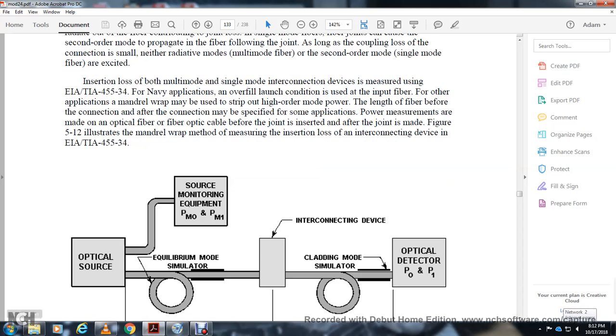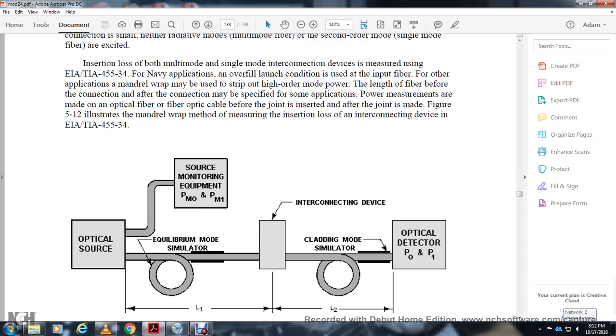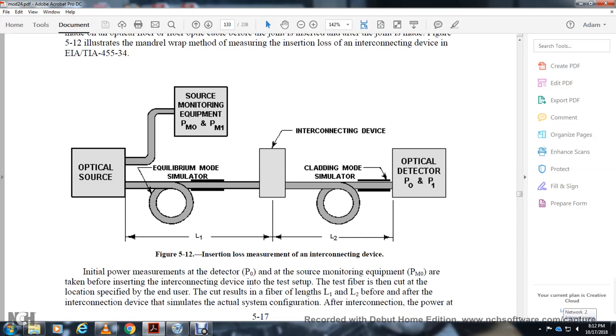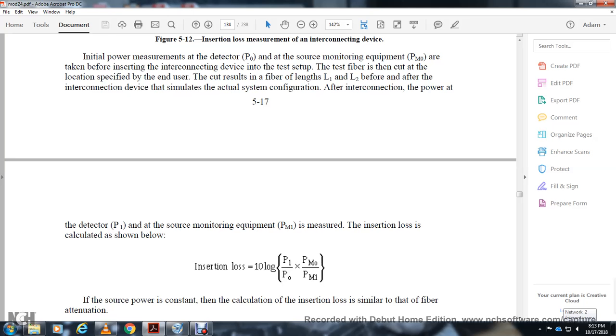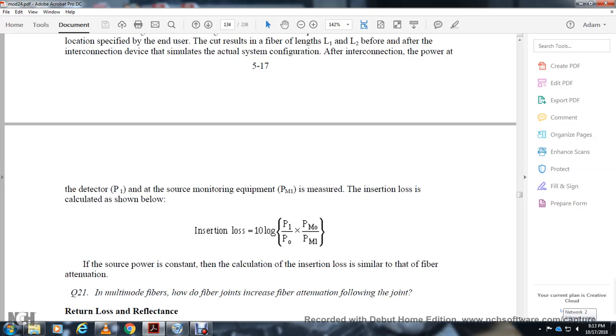Figure 5-12 illustrates the mandrel wrap method for measuring insertion loss of an interconnecting device per EIA/TIA-455-34. The procedure involves measuring power P0 (reference power) with the source and monitoring equipment connected. Then the interconnecting device under test is inserted and power P1 is measured. The insertion loss equals 10 log(P0/P1), or equivalently power 1 minus power 0 in decibels.